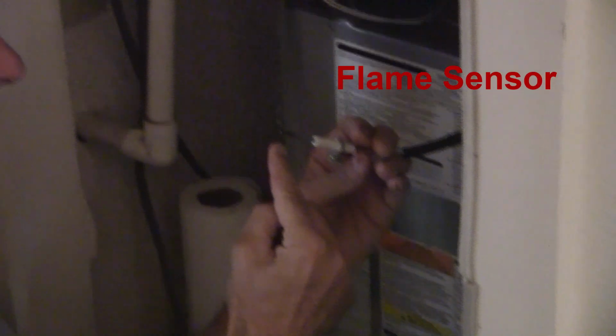All right, so this is the heat sensor, and there is carbon buildup on the heat sensor. I'm going to take my brass bristled brush here, hold that, and I'm just going to clean all the way around this sensor. This should be done just once a year as part of the preventive maintenance, just to make sure that you have a nice flame sensor. Now, before I touched this, I ran the furnace. The furnace ran fine. I'm going to reinstall this, and then I'm going to test the furnace again to make sure that it's making good contact with the flame and that it is making sure that the gas valve comes on. So we'll start it up as soon as we put it in.